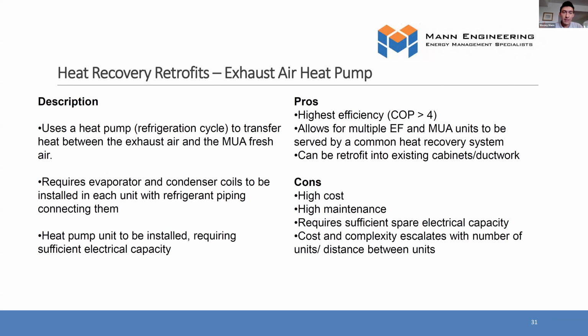Exhaust air heat pump. This is in ways similar to the glycol runaround loop. It allows you to connect potentially multiple units that are separated by a distance. But the main thing is it's using a heat pump. So instead of just relying on glycol as a medium of heat transfer, you're actually using a refrigeration cycle to pump heat from that exhaust air into the fresh air. It can be very, very efficient. You can get COPs of 4 or higher. Basically, that means 400% efficiency, and that is possible with heat pumps because it's not actually generating heat; it's just moving heat. So you can get great heat recovery.